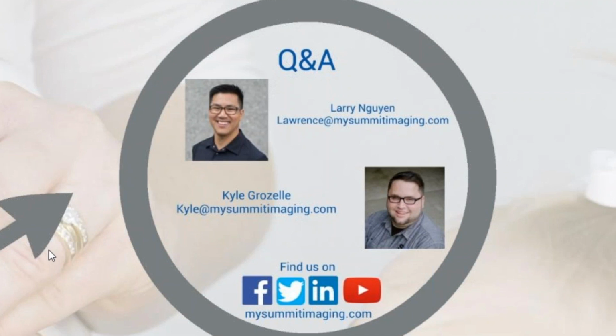Okie dokie. If you discover a hole before the probe is sterilized, how can you clean it thoroughly so it can be sent out? In this situation, speaking for ourselves, we're prepared to decontaminate or disinfect on site. The process you would still want to do at the hospital is a high-level disinfection using soap and water, taking care around that puncture mark. Or even better, if you can use the sterile sani-cloths, preferably purple top or gray top ones that are quite strong. And then make sure when you pack it into the box, it is dried out and that moisture is not traveling around.